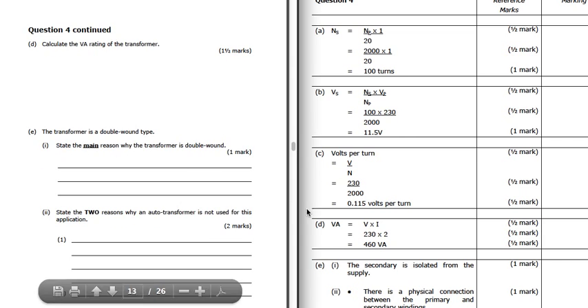The VA of the transformer, because it's just single phase, is just going to be the volts times the current. So again, you can use the values they've given you. 230 times 2, we've got 230 volts on that primary. We're told there's 2 amps flowing, so that's 460 VA.